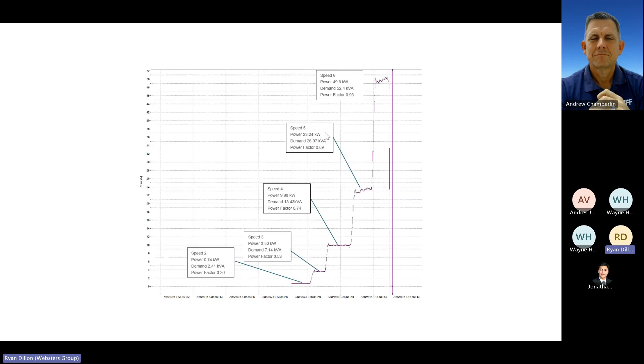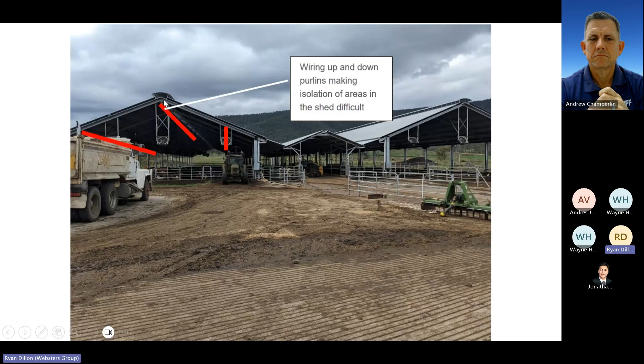And I think we visited site around 5 or 6 times, and you don't find everything on the first visit. So something that popped up to me in this testing was that the wiring is up and down the purlins of the shed, because it's naturally how you'd wire a building, just cables running along. So all of those fans are turned on at once. Now, if only half the cows are in the front of the shed and say they're just all up here, you've got to turn all the fans on at once.